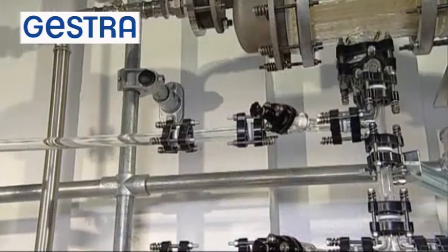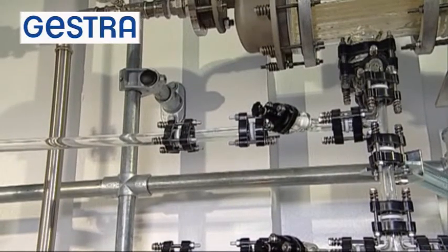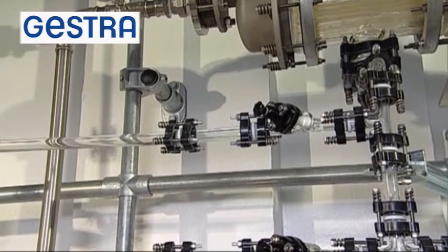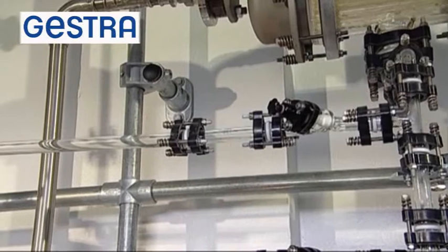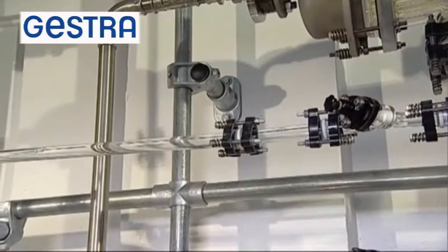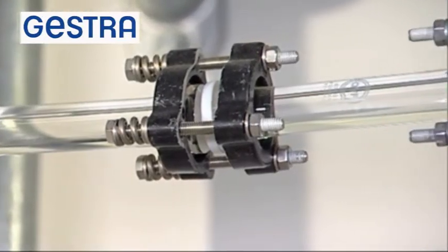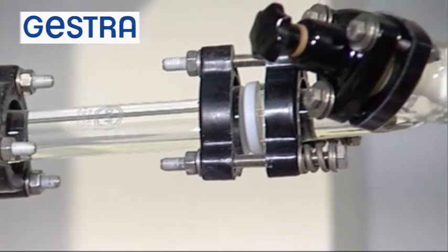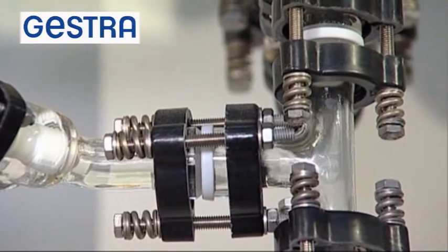In this film clip, the origin and effect of thermal pressure pulses, generally known as water hammer, will be demonstrated. For this, steam is introduced into a horizontal glass tube with a slight upward inclination, thus forming a pocket of water. The water enclosed in the tube on the left-hand side is cold, whereas steam is available on the right-hand side. This represents a typical startup situation for pipe segments with poor drainage.